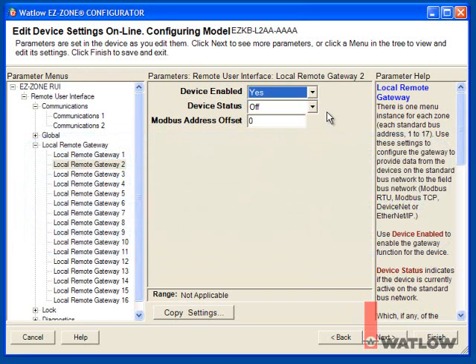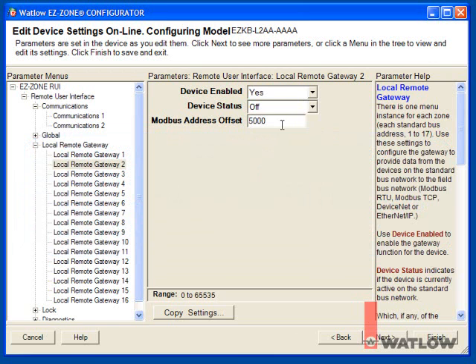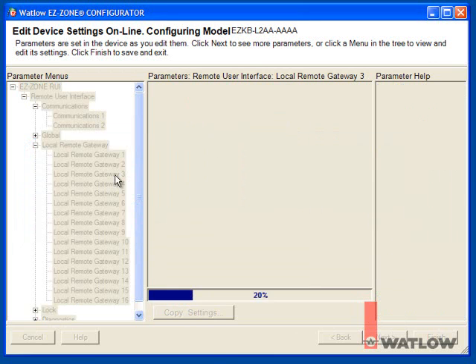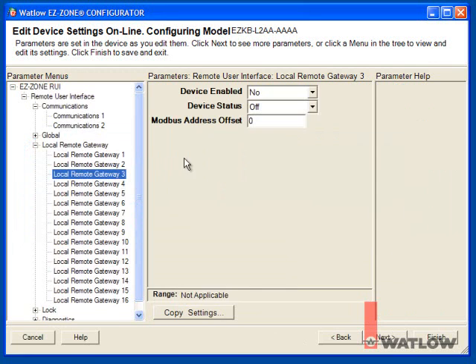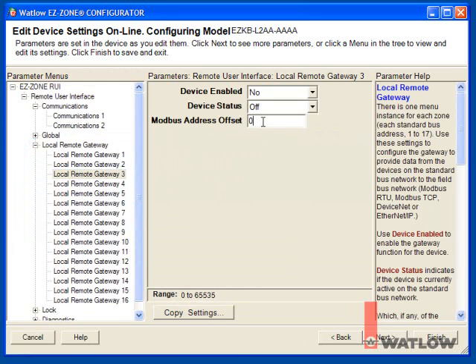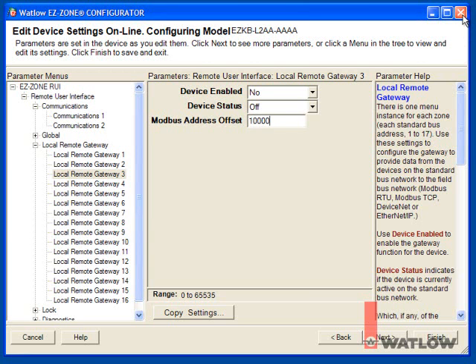Let's set the offset to 5000. That gives us some additional room in case we decide later to access other parameters we haven't anticipated at this point. For the offset for the third module, the scanner module, let's offset its addresses by the same amount so that the same range of parameters is accessible in the two RM control modules. To allow 5000 addresses for the second controller, set the scanner's offset to 5000 higher, 10,000. Close EZZone Configurator.